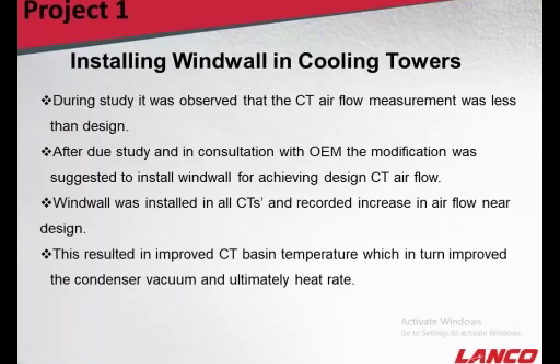So during our study, it was first observed that CT airflow measurement was less than design. So this was a great mistake. I will not say it is a mistake, but it was a problem that nobody took care of during the commissioning stages. So after due study we found the reason why this airflow is less. After due study, in consultation with the OEM, a modification was suggested to install the wind wall for achieving the designed CT airflow.